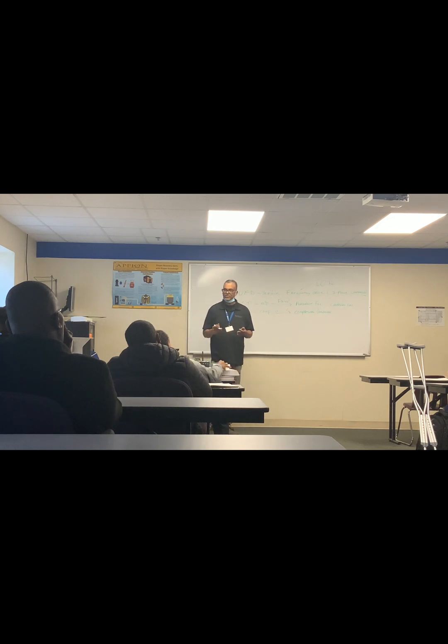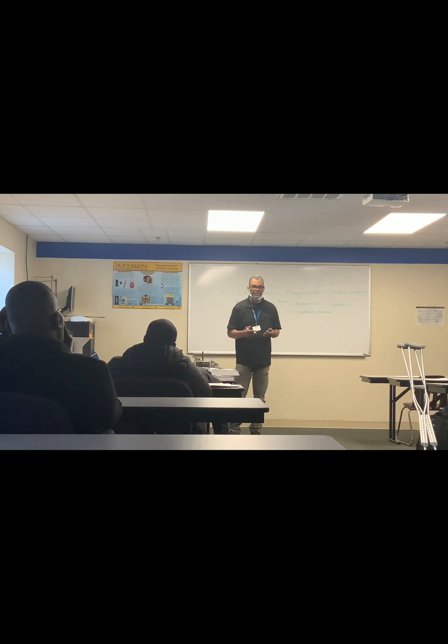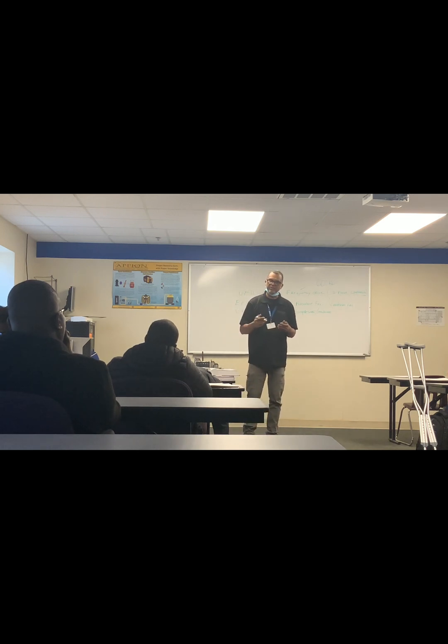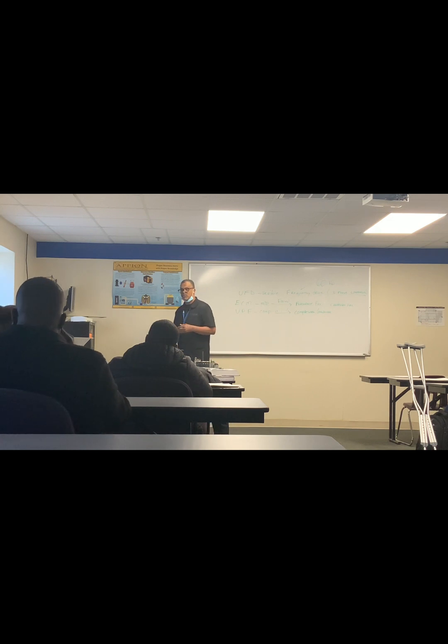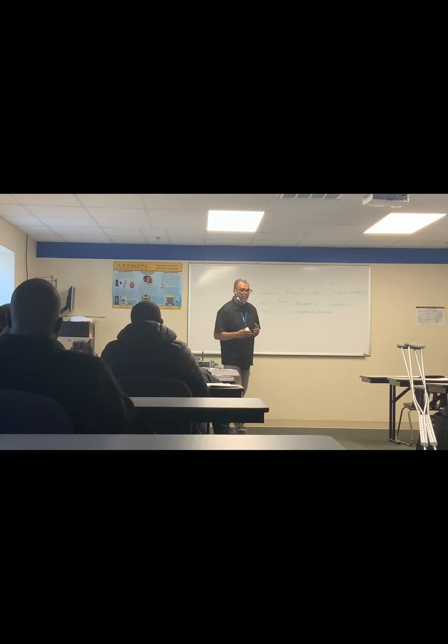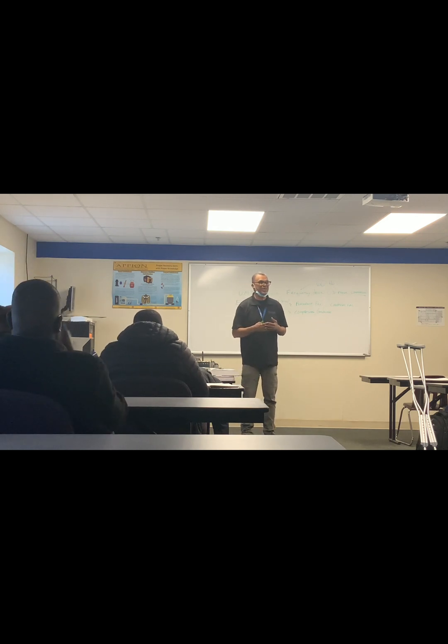So residential said we could benefit from that, but you can't do that with single phase. And so one of our brilliant engineers said, you know what? We can fool, and this is on one of the tests, we can fool single phase to think it's 3-phase by taking it through an electronic module, converting it to DC, and DC can change the speed of a motor, and it won't know it. That's kind of brilliant, that someone actually read the kind of books and understood how to do that. I always think so. And we can change the speed and get the same effect. And I say that because I've noticed over the years, it's been a while, but it's gradually changing more and more, how controls and operation of residential machines mimic commercial.